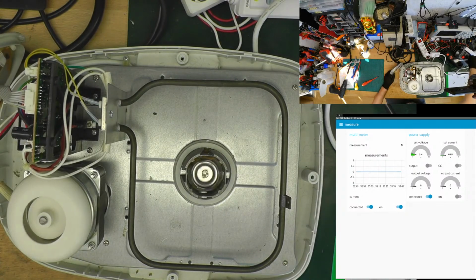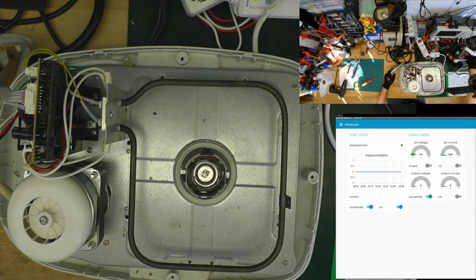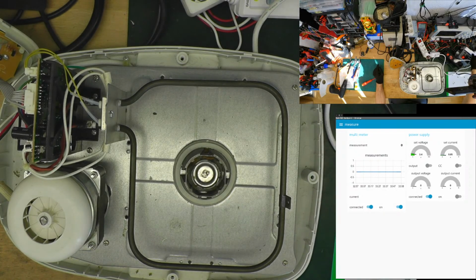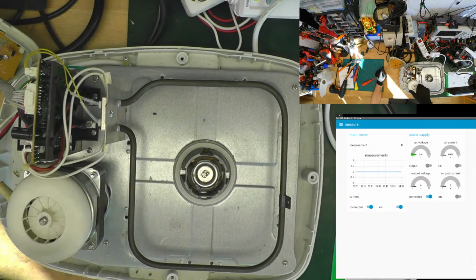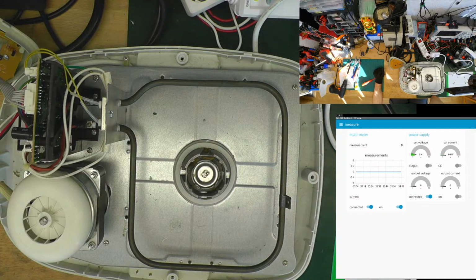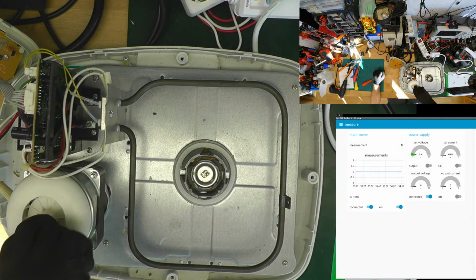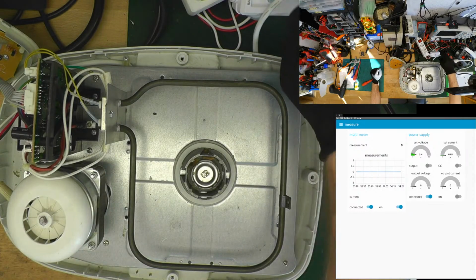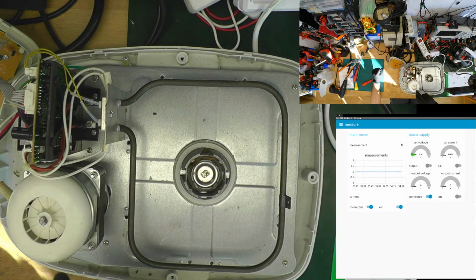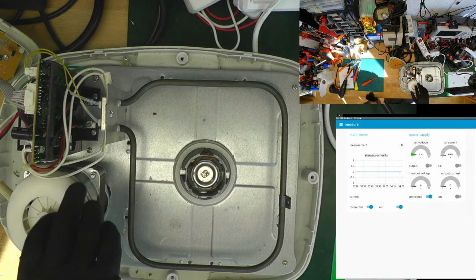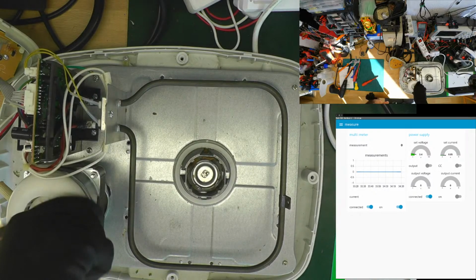Let's switch off, was this it? Yeah, that's all, let's switch it off. Okay, now it's off. I don't know why it would have caused... maybe it didn't, no, the RCD tripped. Maybe the RCD also has a 16 amp fuse, and maybe this also tripped, the fuse. I tested it also here, and this tripped. So the issue was really a leakage, but it came from the motor. The motor is not looking good.